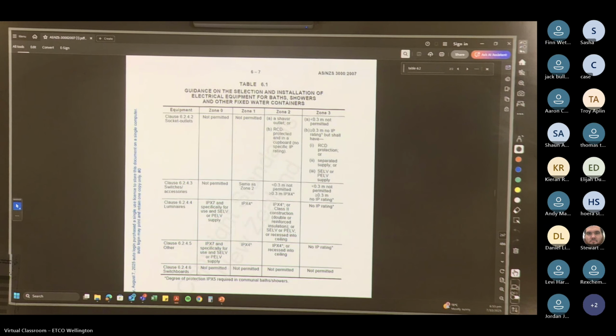So for switches, less than 0.3 meters not permitted. And then equal to or more than 0.3 meters can be IPX4. So IP for luminaires: IPX4 or Class 2 construction, double or reinforced insulation, or again, SELV or PELV, or recessed into the ceiling.